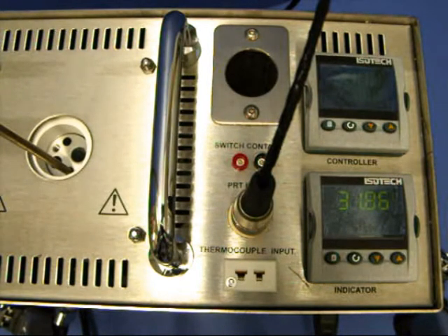The temperature indicator. Site models include an electronic temperature indicator. The indicator can be configured for the desired sensor type and for custom calibration data. The custom calibration data can be set on or off.